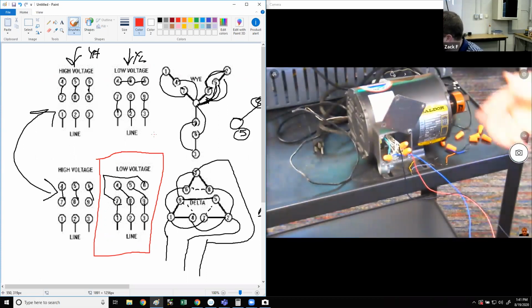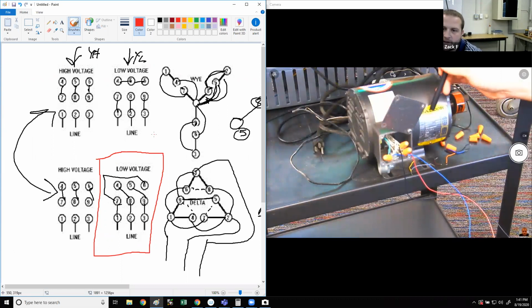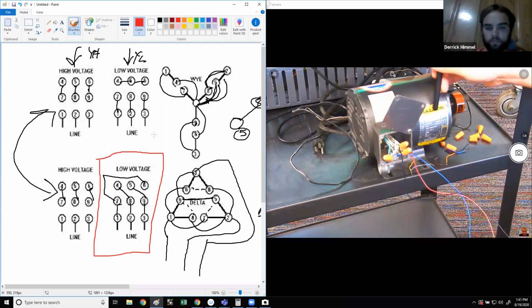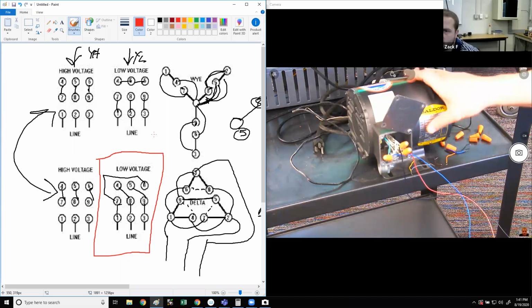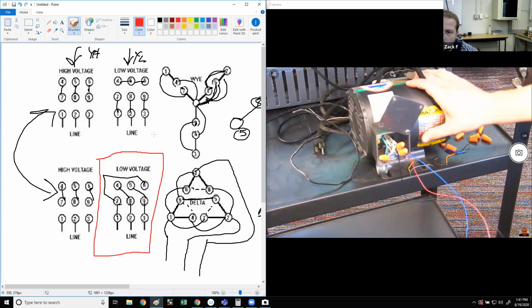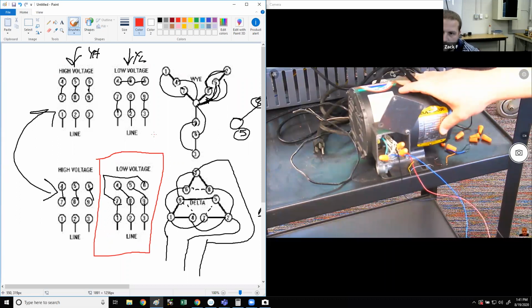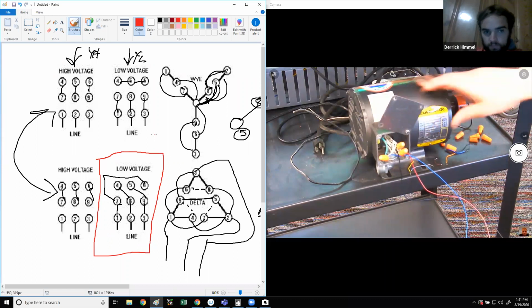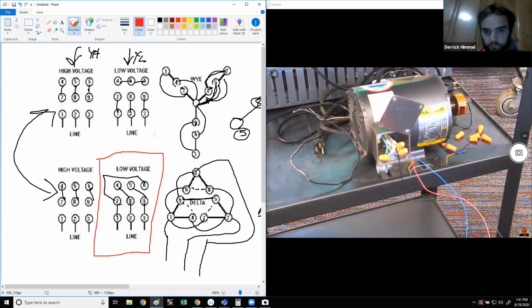So Baldor, this manufacturer has no idea what orientation Ameren is bringing in the phases into your facility, right? Okay. Can't guess. So if we're hooking this up to a pump or a fan, what you would have to do is hook it up, check the rotation, and if it's correct, then you're good. If not, then yeah, you switch 2 leads and off you go. It's a good question, though.